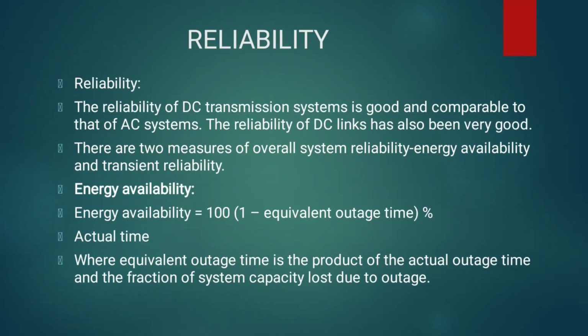Reliability. The reliability of a DC transmission system is good and comparable to that of an AC system. The reliability of a DC link has also been very good. There are two measures of overall system reliability: energy availability and transient reliability. Energy availability equals 100 times 1 minus the equivalent outage time, where equivalent outage time is the product of actual outage time and the fraction of system capacity lost due to outage.